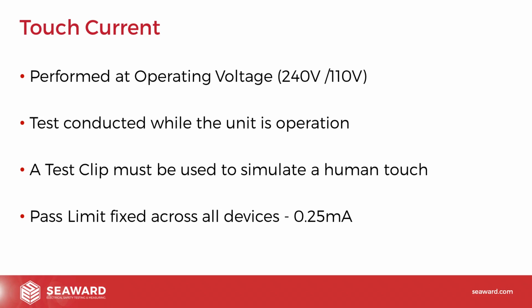Now, for this reason, because we're talking about currents flowing through the body, we have a very strict pass-fail threshold on this test. And in this case, it doesn't matter about the type of equipment we're testing. So it doesn't matter whether it's handheld, portable, stationary. The pass limit for a touch leakage device is fixed across all devices, and that's at 0.25 milliamps. So any current flowing greater than 0.25 milliamps should be deemed a failure when performing a touch current test.